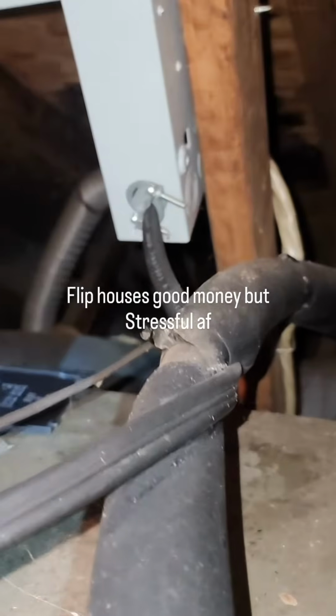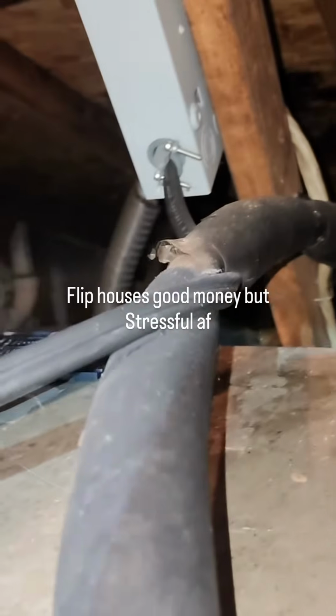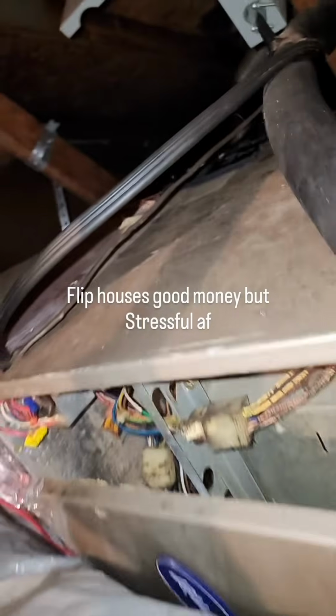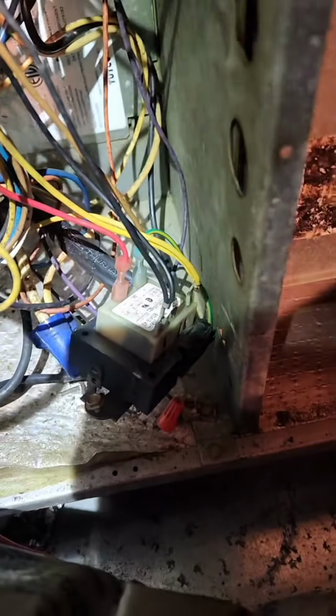Just look at that. That is just crazy. The high voltage snakes around the line set and goes in there. Everything's super tight. Supply duct running across the unit. There's a huge gap of air blowing out the back of the unit. Crazy up there. Alright, so they smoked the thermostat. They smoked the transformer when they changed the thermostat.